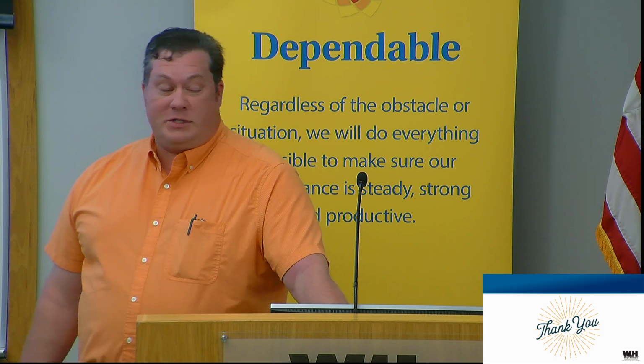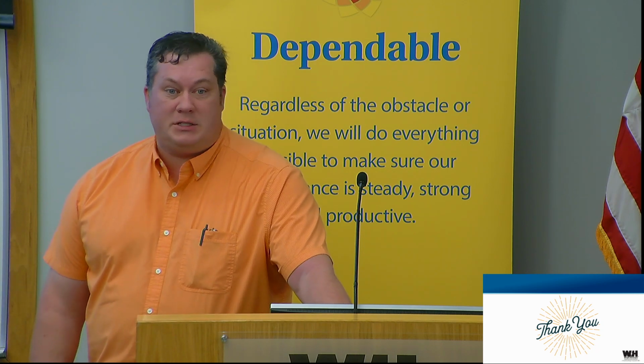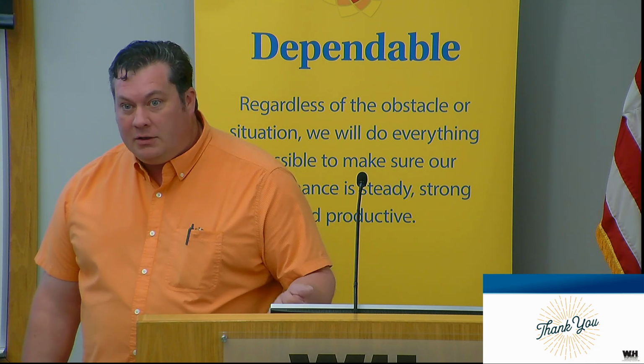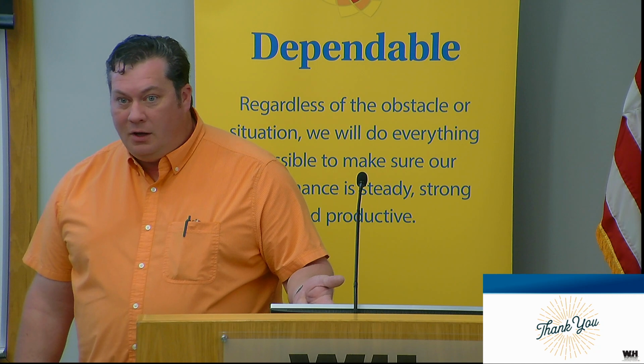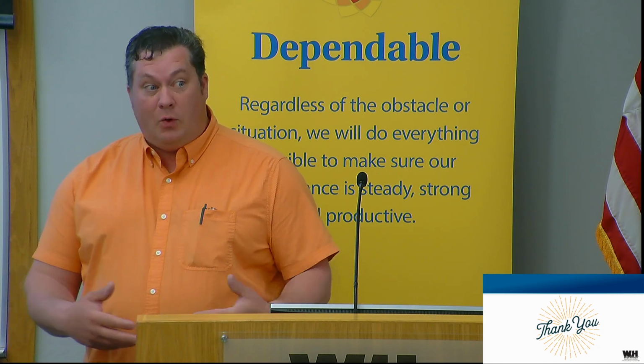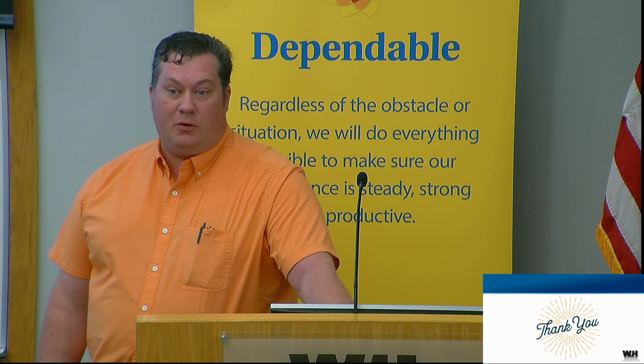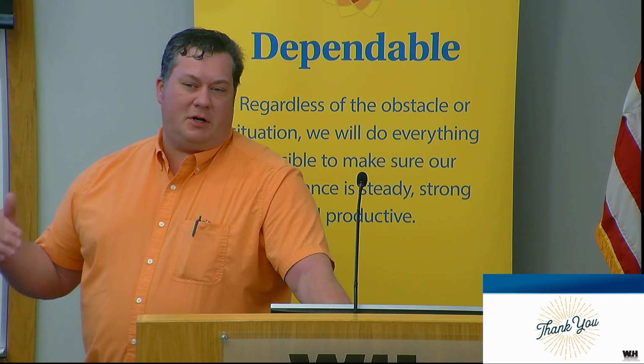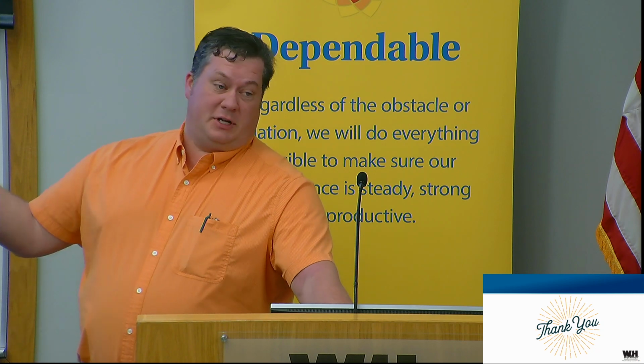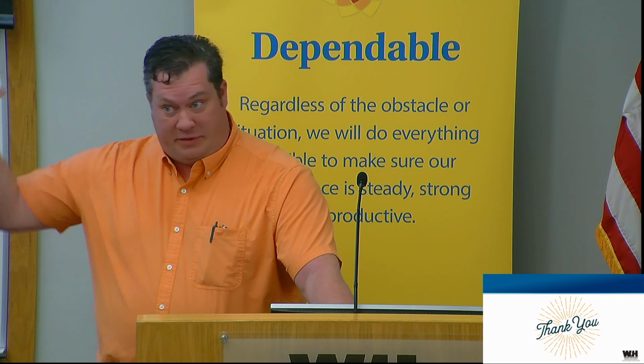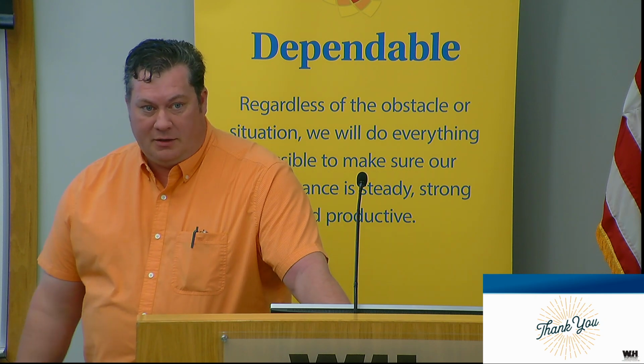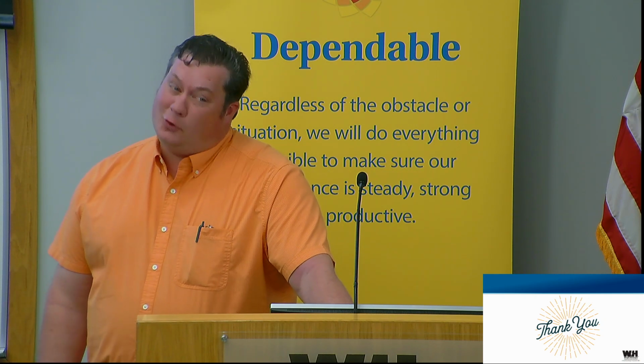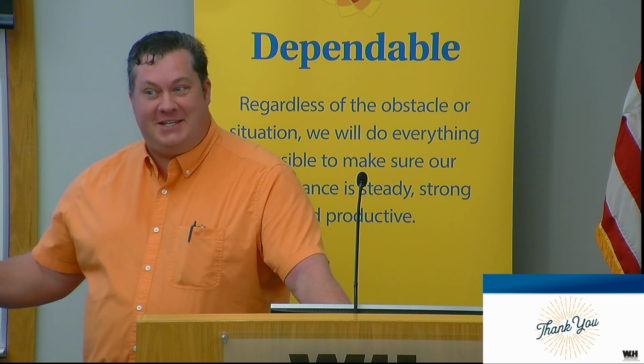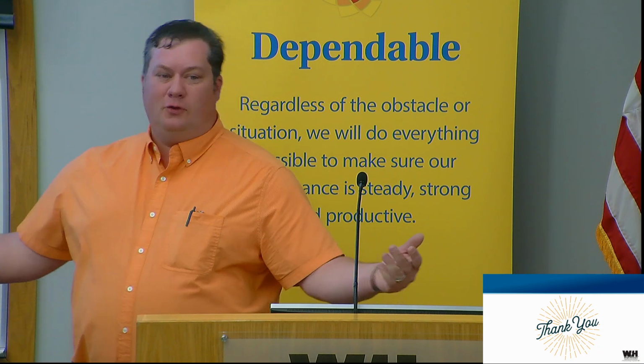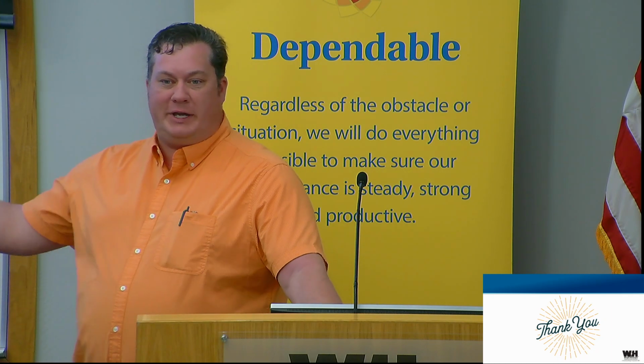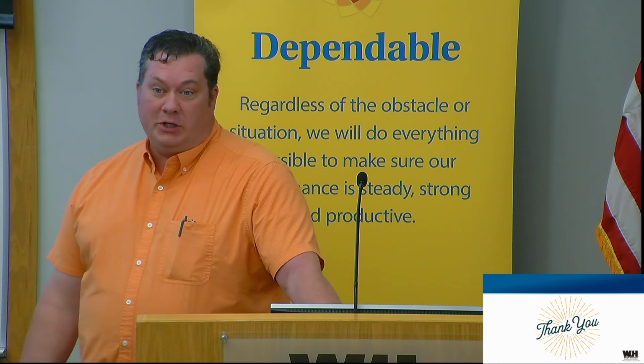So now, how we've been enforcing it for probably 6, 7+ years: that thing's gotta meet arc fault, gotta meet ground fault, gotta meet tamper-resistant, all the provisions, gotta have equipment grounds. So when you move in an old house, you might be redevicing the whole thing or even rewiring some of it. It even goes as far as light fixtures - if a fixture needs 90°C wire and you've got old NM that's not rated 90°C, that's an issue too. I don't know too many inspectors who are gonna check that one, but I'm just telling you, it's in the bulletin. I'm not gonna grab a ladder and check what a fixture's rated versus the old NM in an existing house, but the bulletin tells you otherwise.